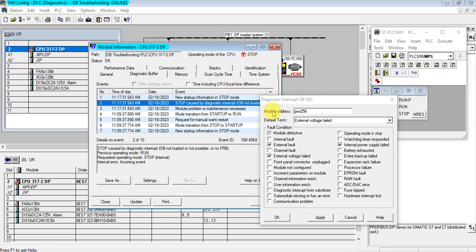As you can see in the diagnosis buffer, the CPU was stopped by diagnostic interrupts because the OB is not loaded. We can resolve this problem by adding OB82. Let's add OB82 and see the result.